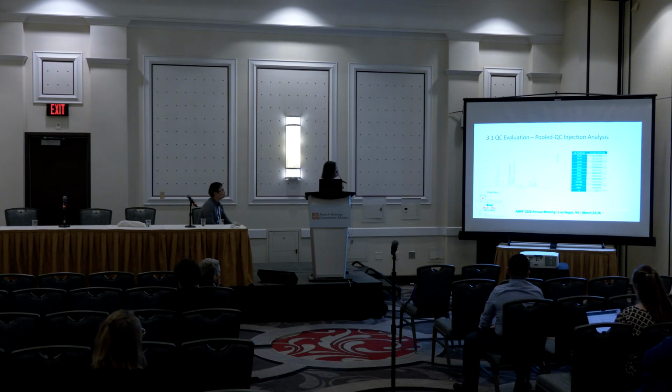You look at the figures, the 9 QCs overlaid really, really well. I observe very, very minimal shift of retention times. I also check the overlay of intensity and the average intensity of my 9 QCs. You can see the CV is really small, it's 1%.